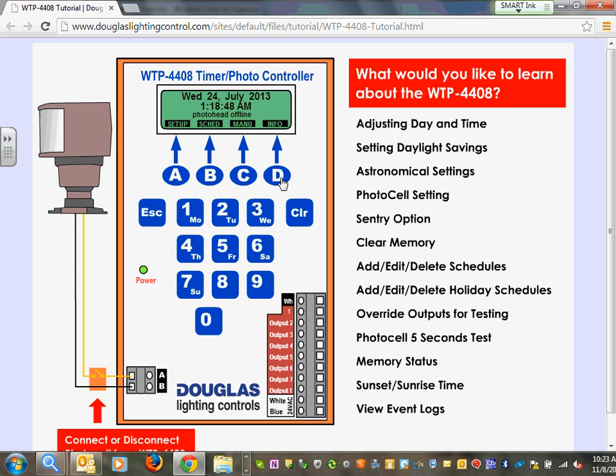So if I want to incorporate daylight sensing, I can put a sensor at that window, read foot candle levels, and then switch whatever I want to, right? Without having to go all the way down to putting a device per fixture. So it gives us huge amounts of flexibility inside of these plants. This is a combination. Both have their pluses and minuses, right?